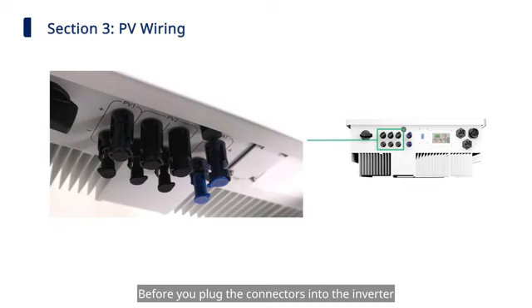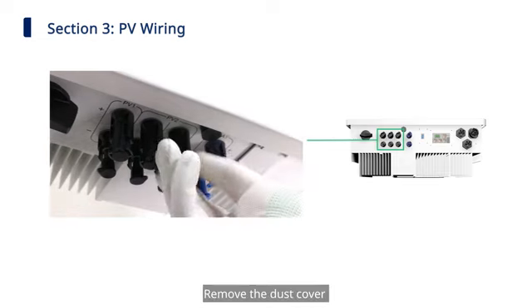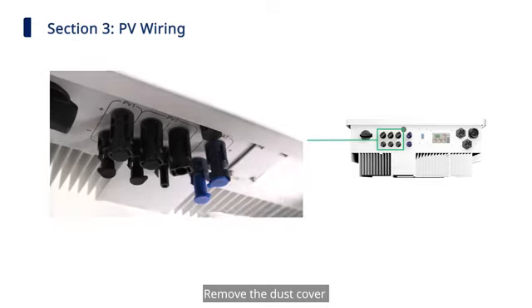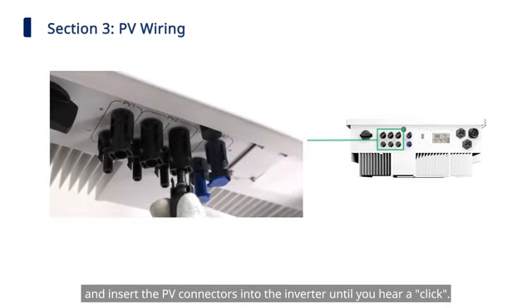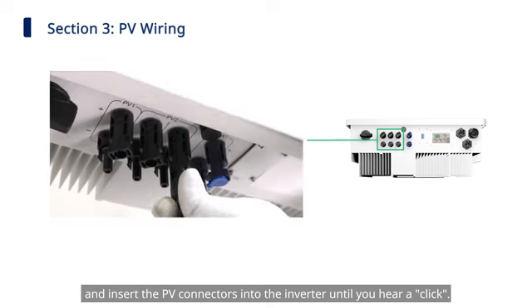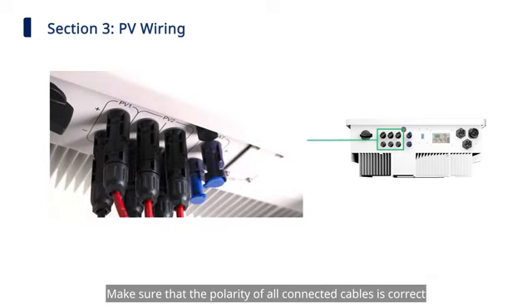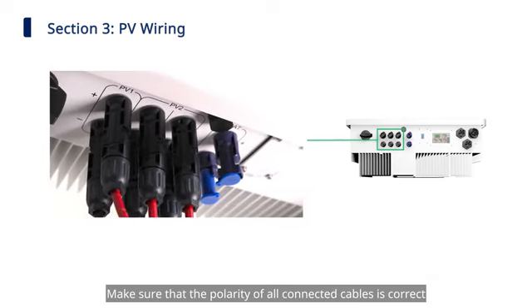Before you plug the connectors into the inverter, make sure the DC switch is off. Remove the dust cover and insert the PV connectors into the inverter until you hear a click. Make sure that the polarity of all connected cables is correct.